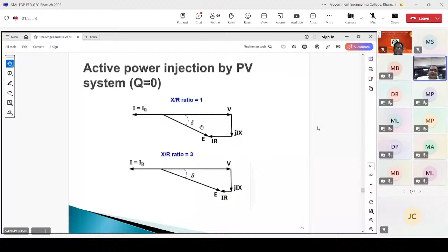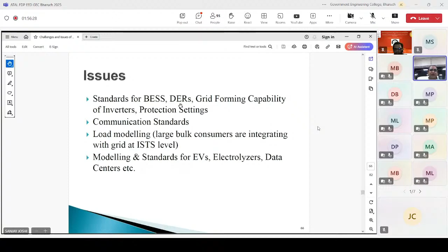What are the issues? Standards of BESS, DERs, grid forming capability of inverters, protection settings - this is required. Communication standards, load modeling standards for EVs, electrolyzers, data centers, etc. - they are all required.